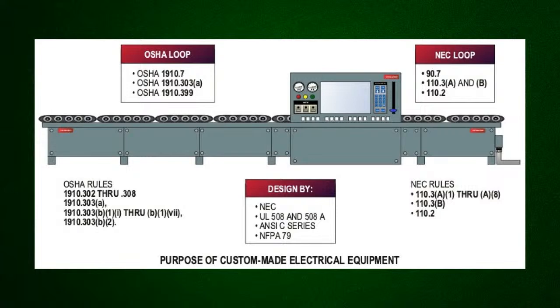You've heard me say this when we were discussing if the NEC overrode it. It says it's designed by what? The NEC - it tells you, and if it was Canadian, it'd be the Canadian code, but here we're talking NEC. They have to take that into consideration, and then look at their other two standards that they'll use: UL 508 and 508A. These testing standards become an ANSI C series, and for industrial control equipment, look at NFPA 79.